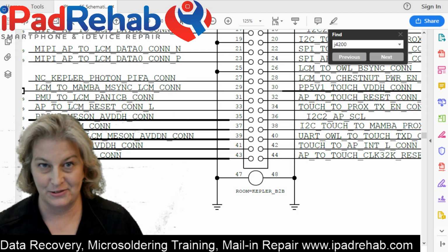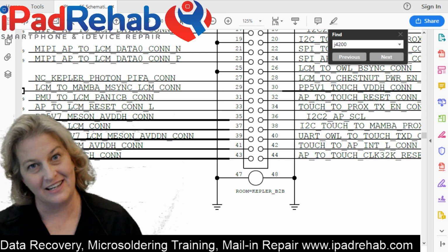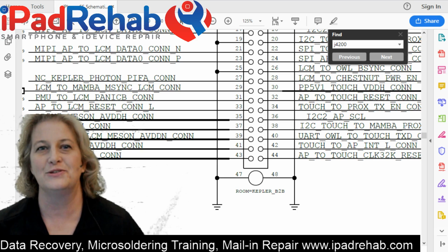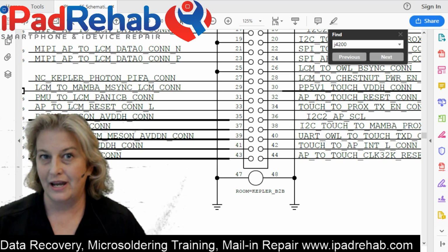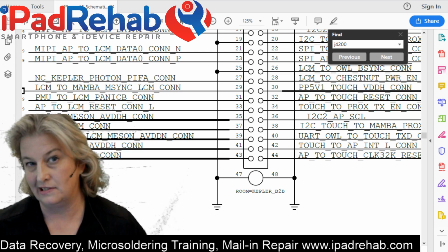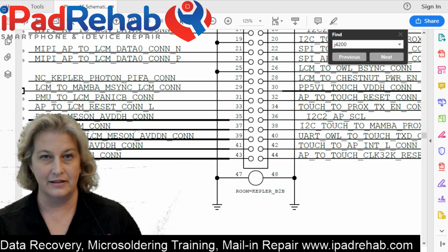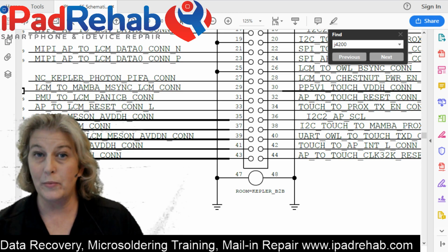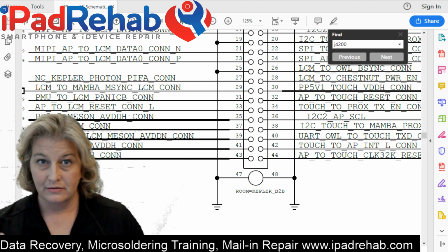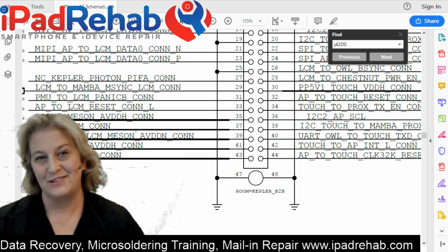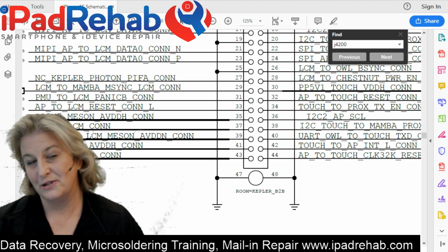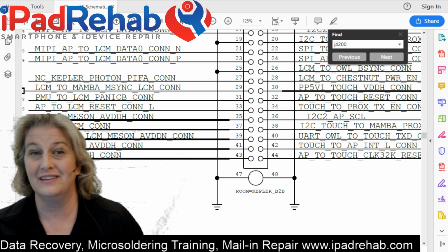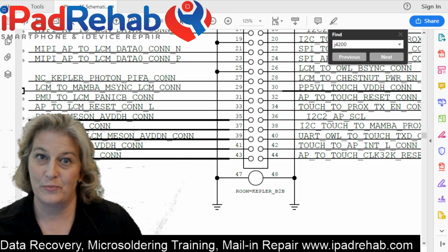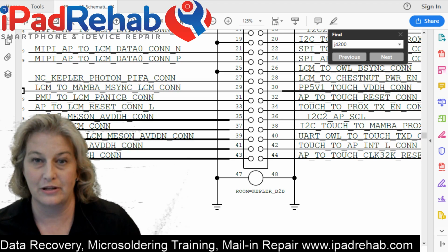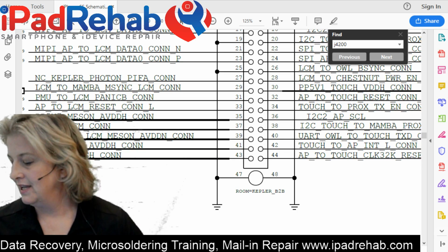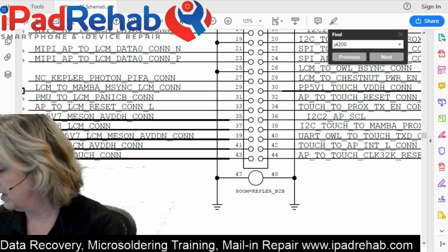We can do our favorite diode mode test. A diode mode test is going to be an indirect way to look at the overall resistance of these lines. Because remember, how do lines fail? They can become short, they can become open, or the guy upstairs is not doing his job. And that's really the only 3 ways that something can fail. So we can really quickly detect short and open just by going down the connector with red probe on ground and black probe comparing values.